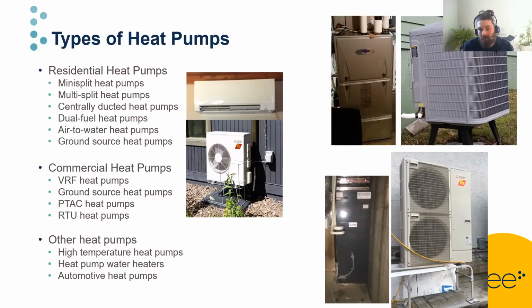We also have air to water heat pumps. So all these examples I gave right now are typically air to air. There's forced air inside your building that's moving around energy, and then it's scavenging air with an outside unit that gets its air from the environment. If we instead replace the indoor unit with a water loop, we can now heat a house that has a hydronic distribution system where it gets boiler heat. So heat pumps work in those applications too.